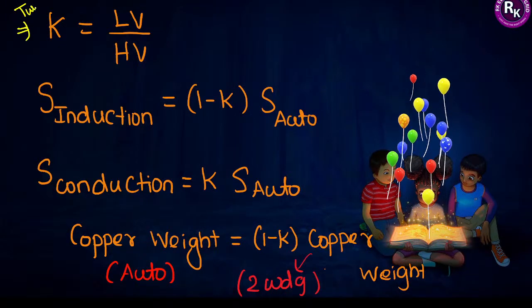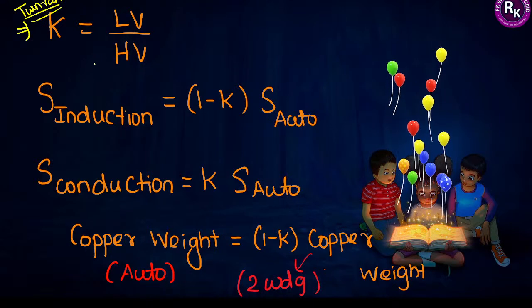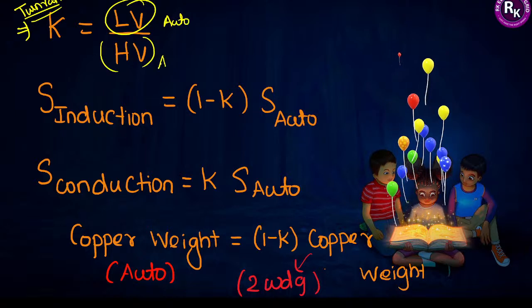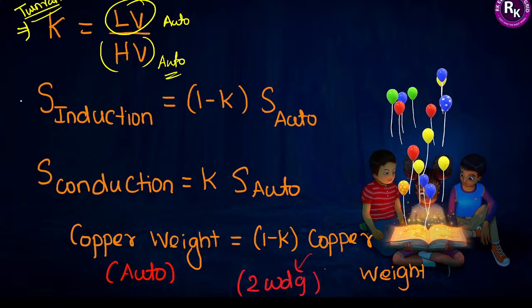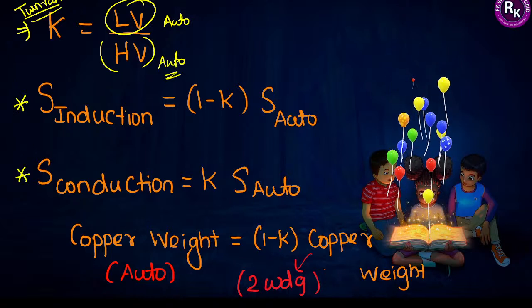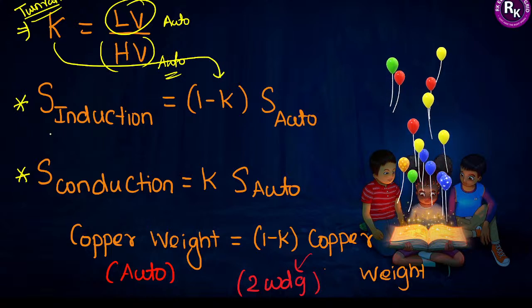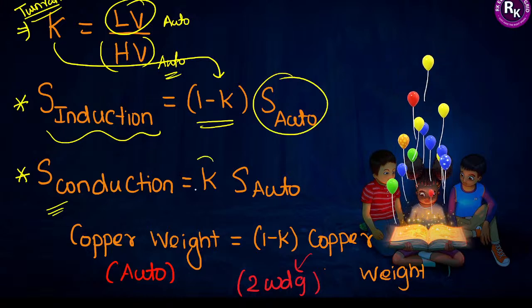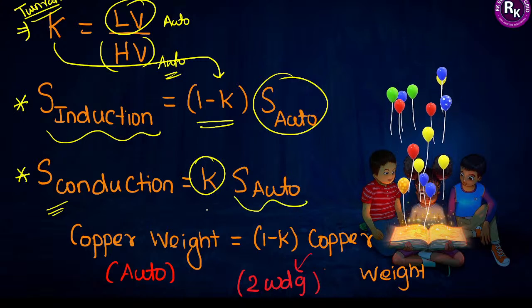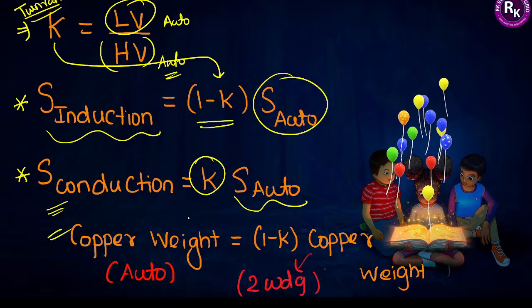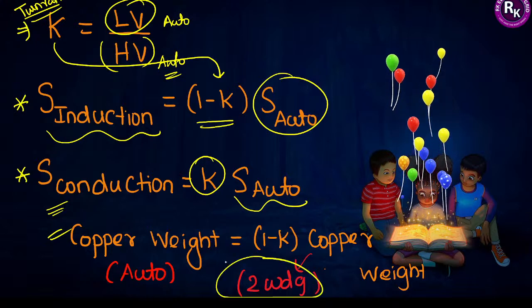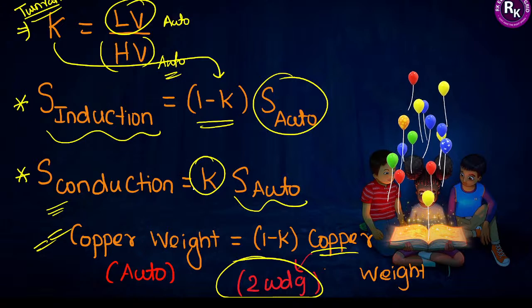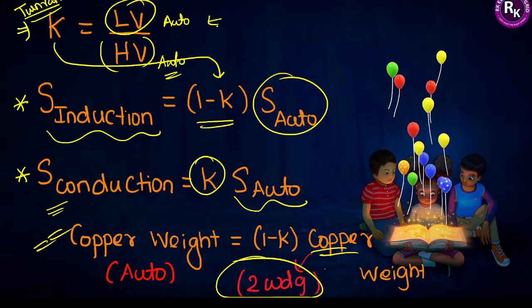In the auto transformer, the turns ratio K is defined as the ratio of the low-voltage winding value to the high-voltage winding value of the auto transformer. Using K: inductively transferred apparent power = (1 − K) × total KVA rating of the auto transformer, and conductively transferred power = K × total KVA rating of the auto transformer. An important exam question involves copper weight: copper weight of auto transformer = (1 − K) × copper weight of the two-winding transformer.